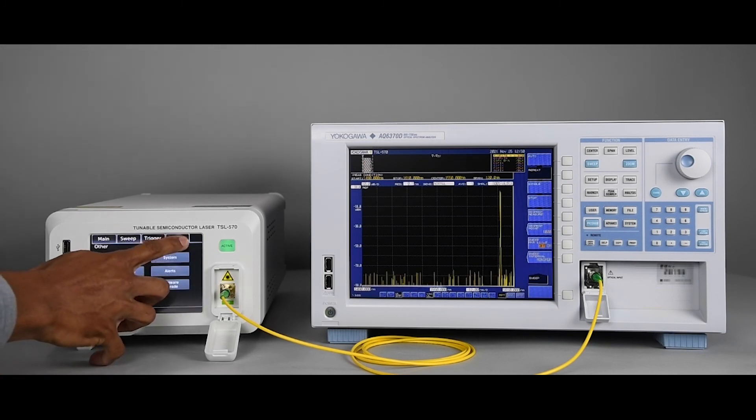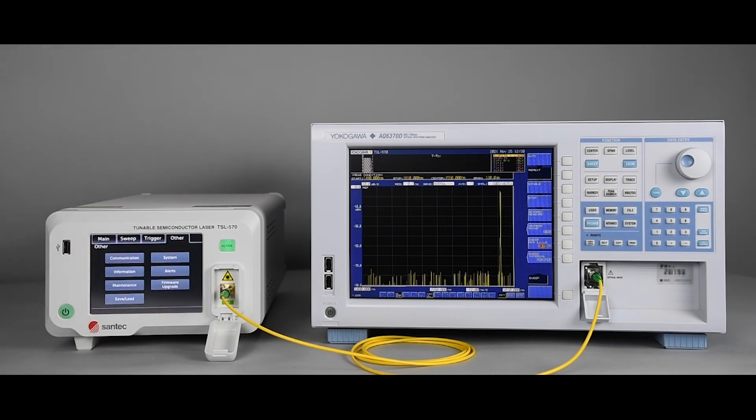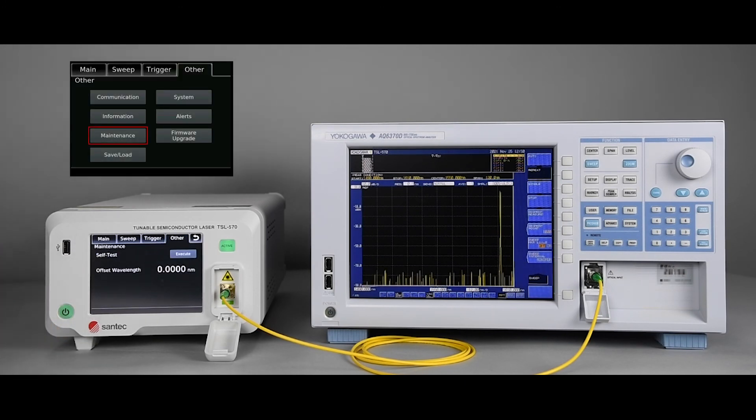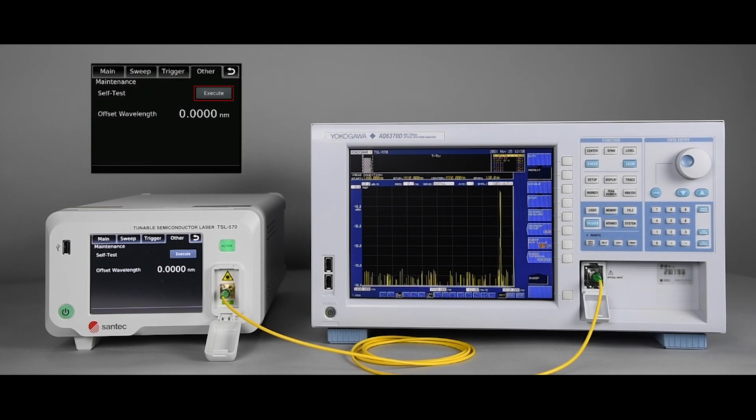On the other tab, it is possible to display and configure different items of the TSL 570. One important feature that Santec provides is the option to run a self-diagnostic test from the maintenance menu. By tapping on the execute button from the self-test menu, the laser will execute a set of examinations and report any malfunction.